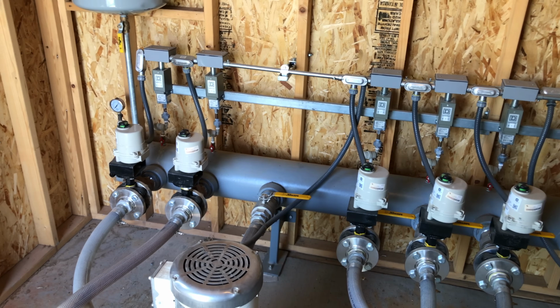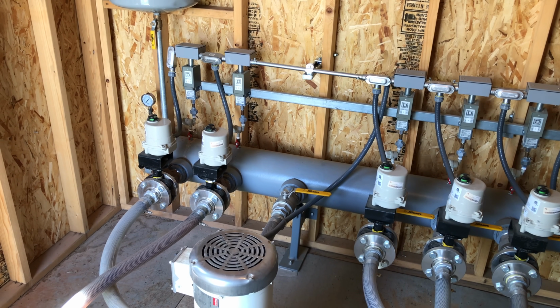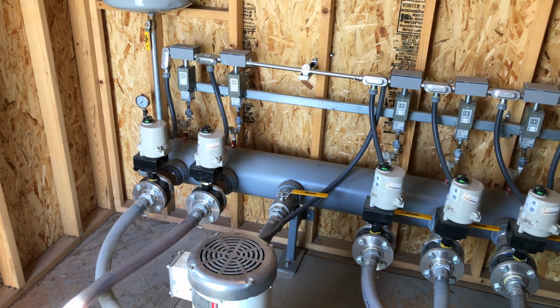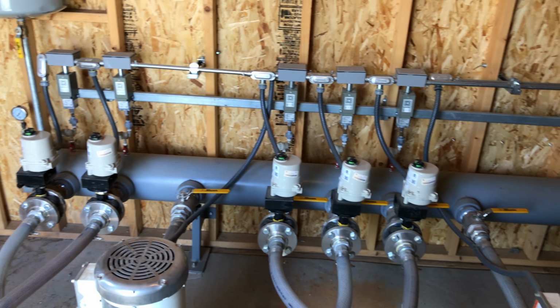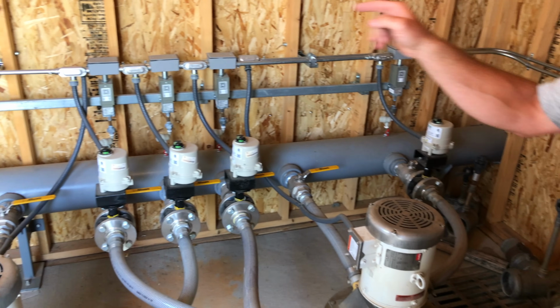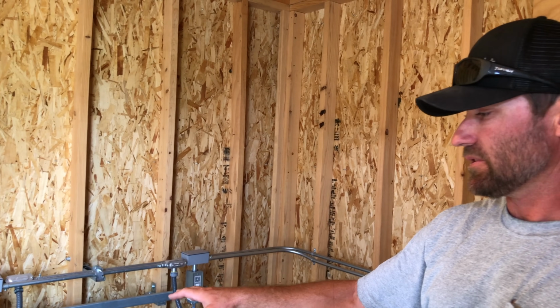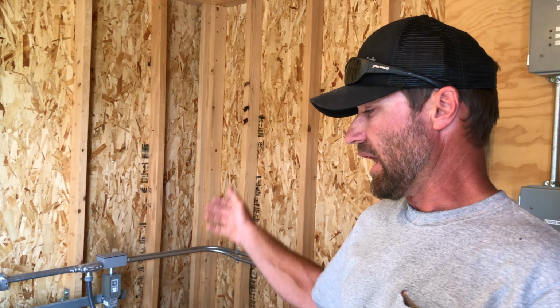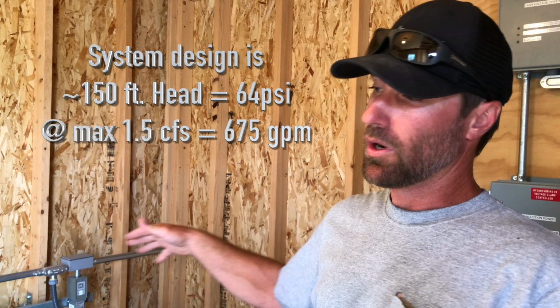So if, say at this property, more water is being used in some of the center pivot irrigation, that means that there will be less water in the penstock above this system. That will lower the head pressure in the line, and these switches will open and close these valves based on what's happening there. So that way we ensure that no water is wasted coming through the property.